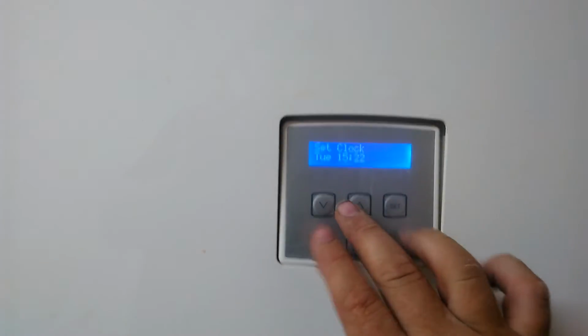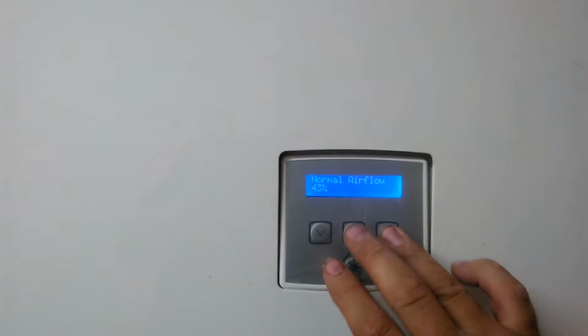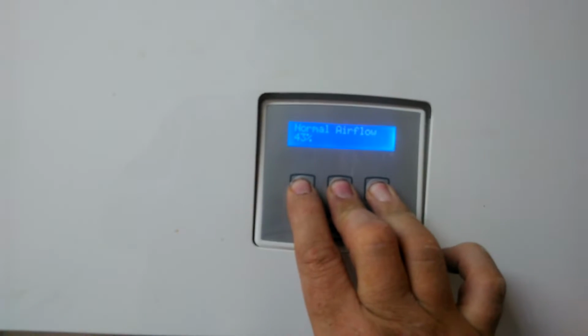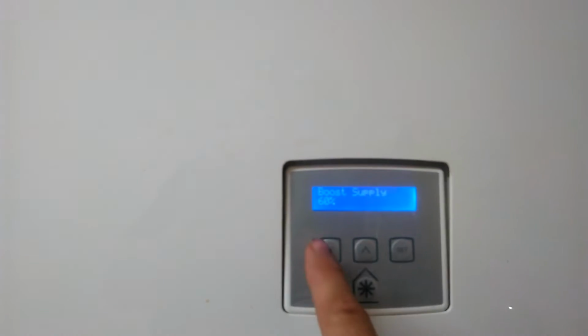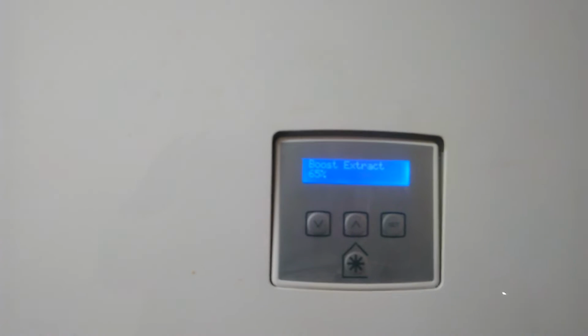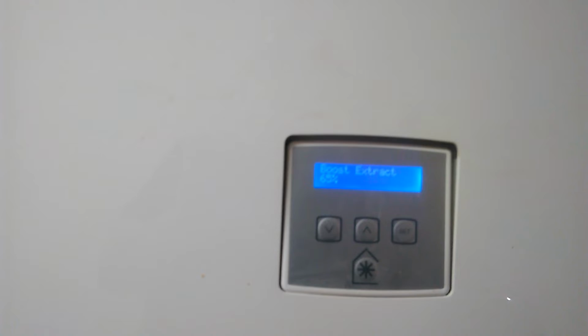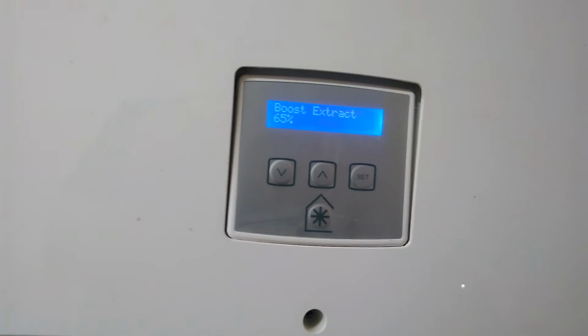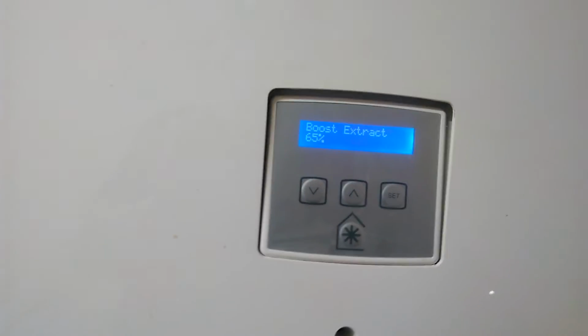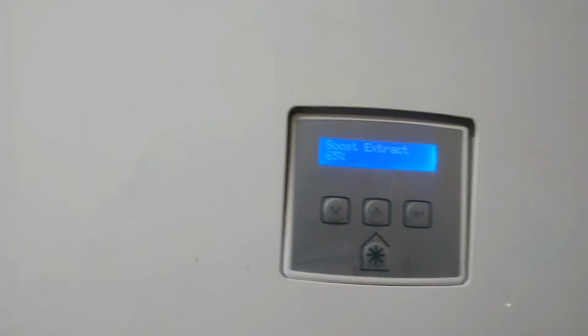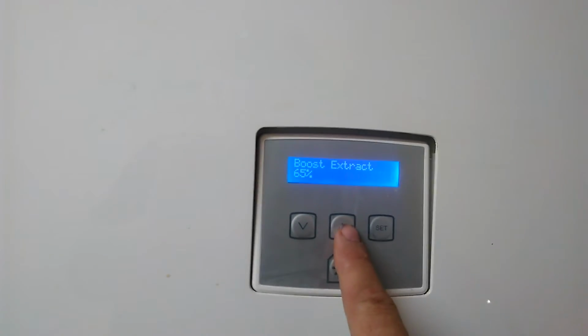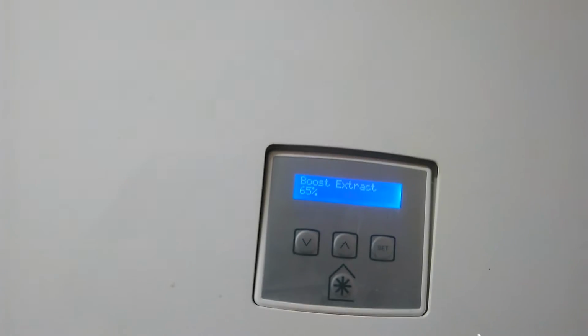To do that, we get it into the normal airflow mode and then we press all three buttons. So we've got the boost supply, and that's set at 60%. We've got the boost extract, and it's higher because the system needed balancing. That may mean that the ducts are longer on the extract side, so the fan speeds had to be increased on the extract to compensate for the resistance which has been placed on the ducting. Okay, so that's quite usual to have a difference on the fan speeds.